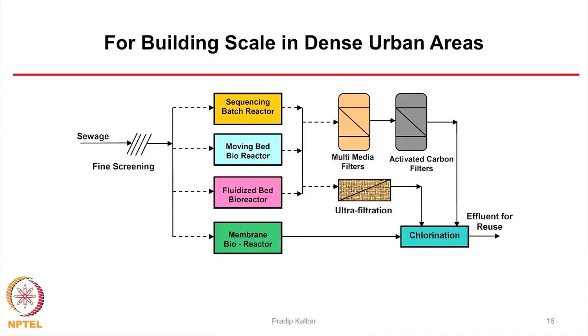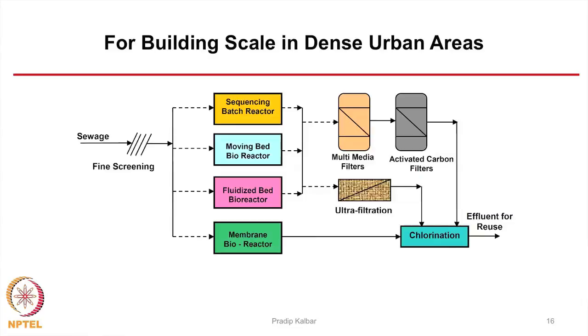Okay, so first is organic load, but that will not be enough if you want to reuse, because if you are making so much investment, our objective should be to reuse and recycle the wastewater. So you can see here the multimedia filters, the activated carbon, these kinds of additional systems you can place for removing the solids, so that at least the treated effluent looks pure. And then you have the ultrafiltration modules also, and I'll show you one of these examples.